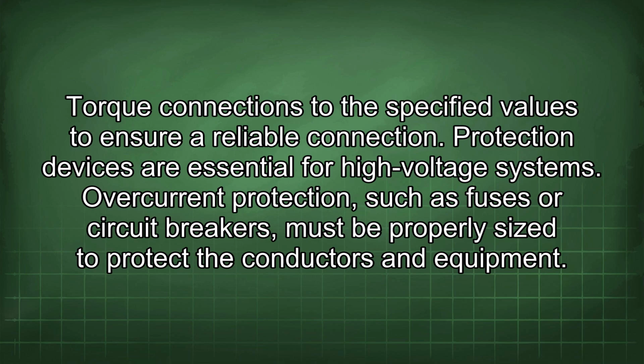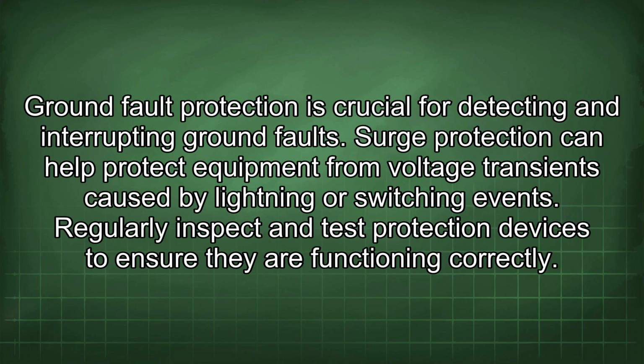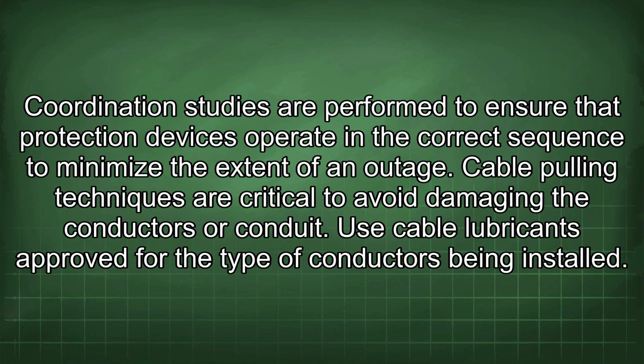Protection devices are essential for high voltage systems. Overcurrent protection, such as fuses or circuit breakers, must be properly sized to protect the conductors and equipment. Ground fault protection is crucial for detecting and interrupting ground faults. Surge protection can help protect equipment from voltage transients caused by lightning or switching events. Regularly inspect and test protection devices to ensure they are functioning correctly. Coordination studies are performed to ensure that protection devices operate in the correct sequence to minimize the extent of an outage.